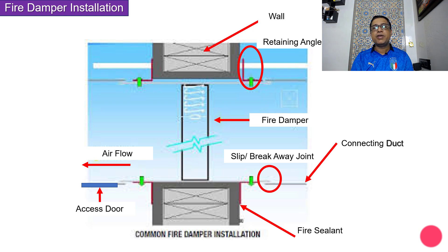When we have two zones separated by a wall, those walls need to be fire-rated walls. You cannot have a fire damper on non-fire-rated walls, which will collapse in case of fire — the fire damper cannot do anything and fire will pass through anyway. So the first important thing is to know which are the fire-rated walls. The fire damper has to be inside or along that wall.